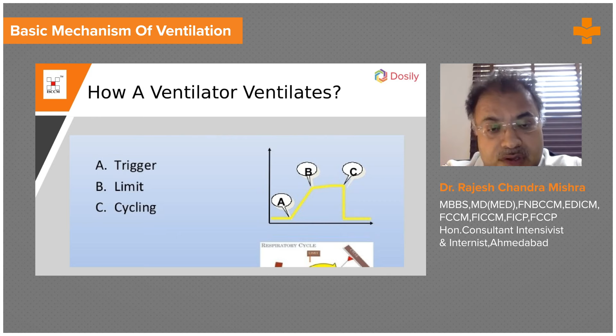Based on TLC, there are different kinds of mode. Once you have selected the mode, you can set the limit in the ventilator. If you go by basic physics, there is a volume and there is a pressure. The ventilator gives you the liberty of limiting one thing: either you can limit the volume or you can limit the pressure. If you limit the volume, it becomes volume control, volume support. If you limit the pressure, it becomes pressure control, pressure support, assist control. So control can be pressure or volume, support can be pressure or volume, assist can be pressure or volume, depending upon what you have limited.